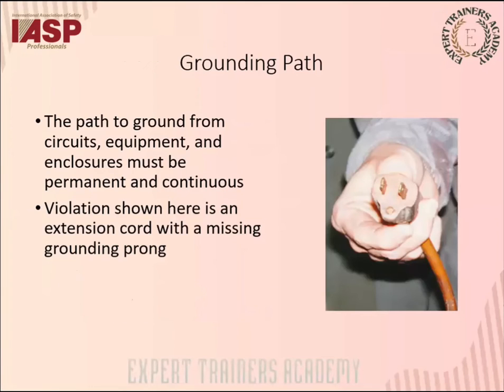Grounding path. The path to ground from circuits, equipment, and enclosures must be permanent and continuous, so inspection must be carried out by a competent person. There is a violation shown in this slide on the right side of your picture: an extension cord with a missing grounding prong. These are the typical plugging systems which are used predominantly in the USA. Our plugging systems are entirely different, like in India.